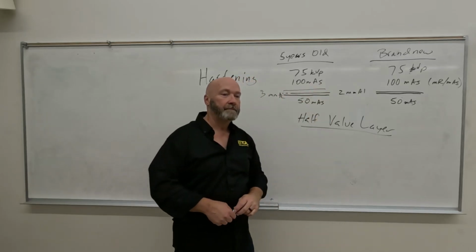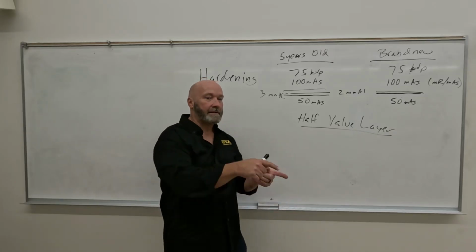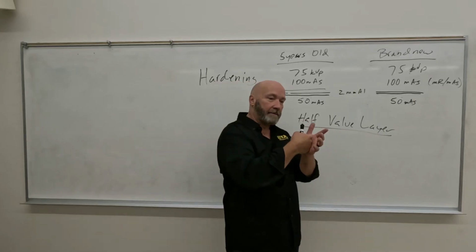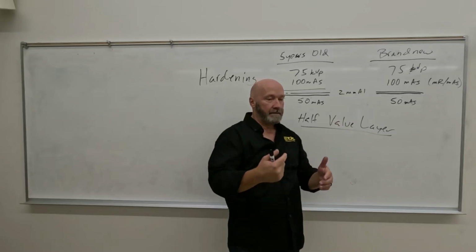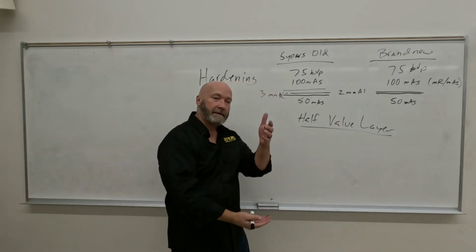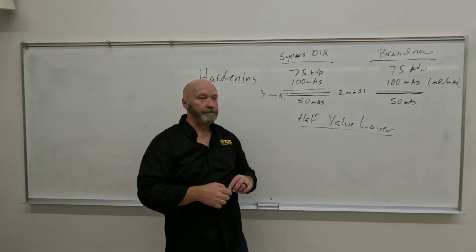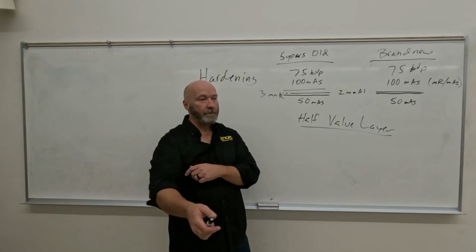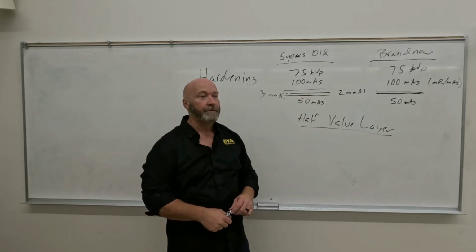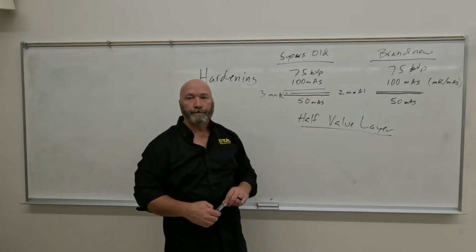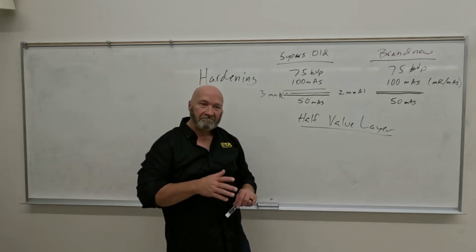Adjusting the mAs? Yeah. They're adjusting the mAs so you still see the same mAs, but what's created at the anode is more, to compensate for what's coming out. So what they're trying to maintain is what's actually coming out, not necessarily what's being created. So you read 100 mAs even though it could be 150, but they're actually still getting 100 mAs. Right, what's actually coming out of the tube is the 100 mAs value. Everybody okay with that?